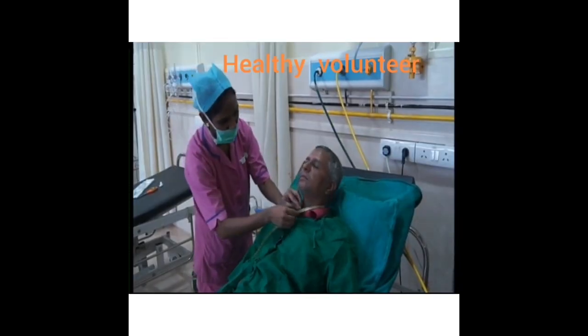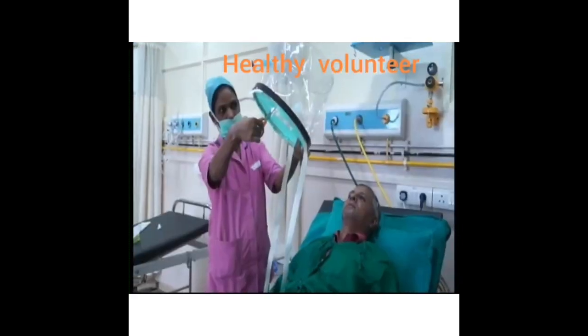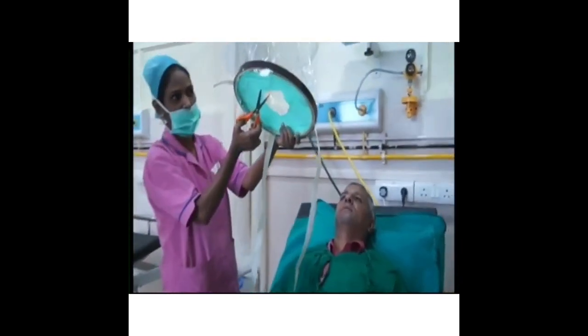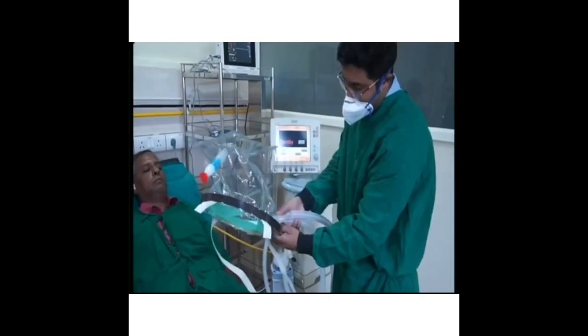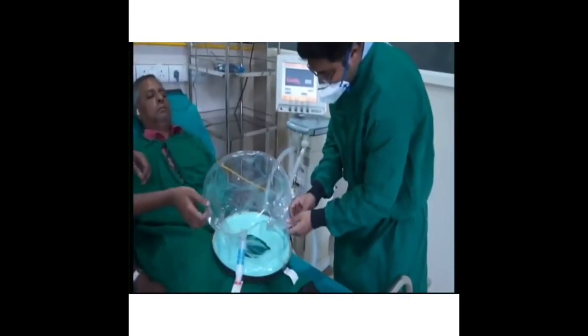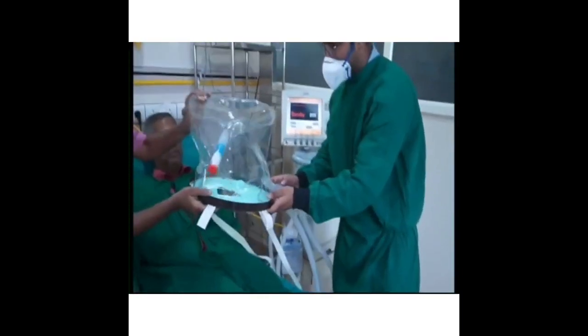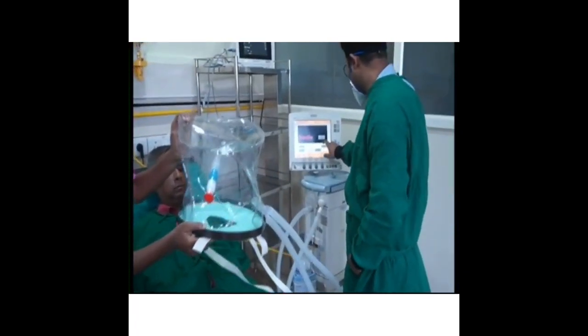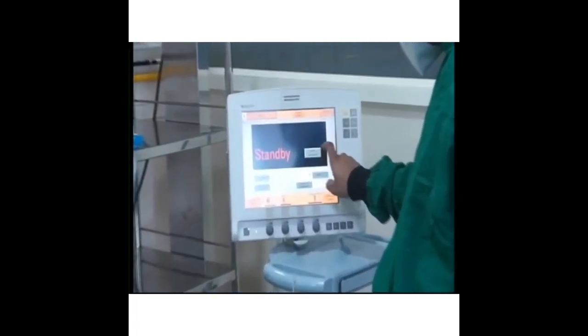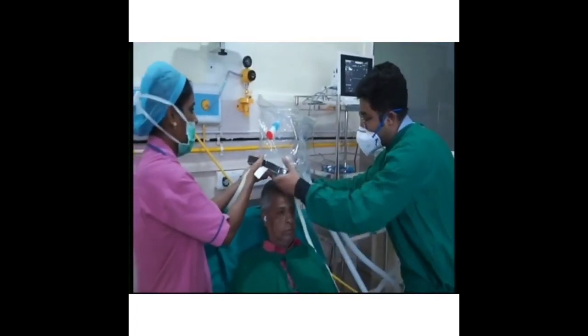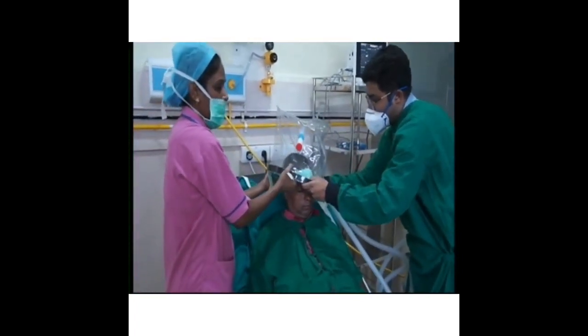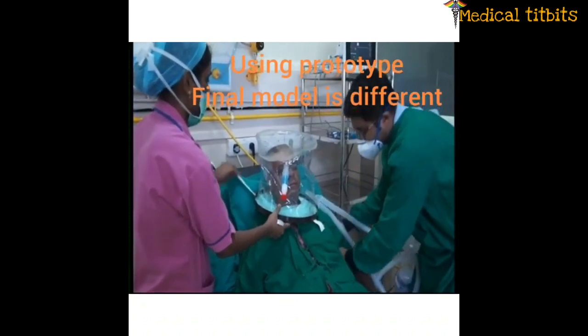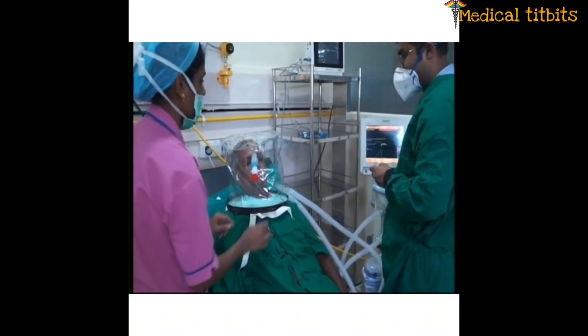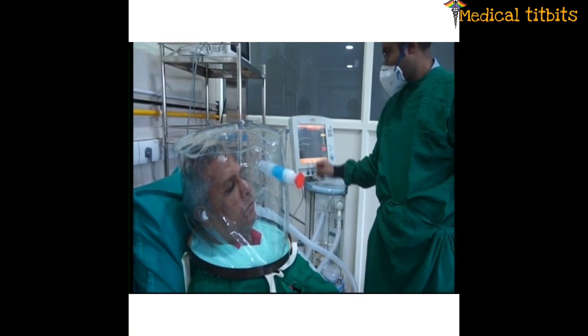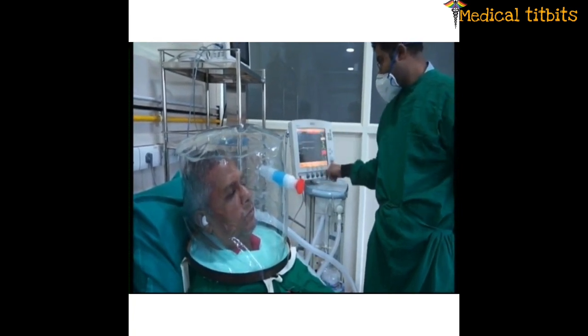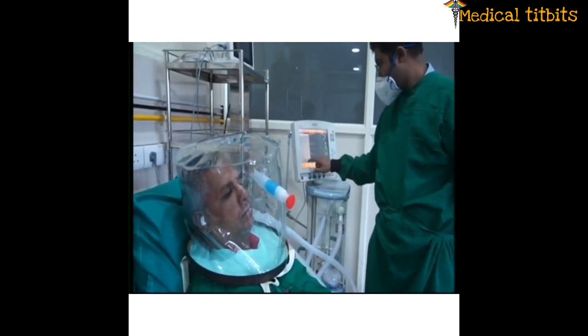Now, how to install it on a patient? First, measure the neck size of the patient. Cut the silicone neck collar according to the template. Attach the ventilator inspiratory and expiratory tubing to the helmet. Set the ventilator to pressure support mode with PEEP of 8 and FiO2 to 60%. Stretch the silicone collar of the helmet, place it over the patient's head and secure the straps. The helmet pressurizes in seconds. For removal of the helmet, the straps are detached and the helmet can be easily removed from the patient.